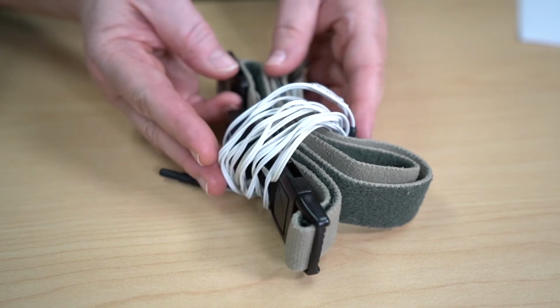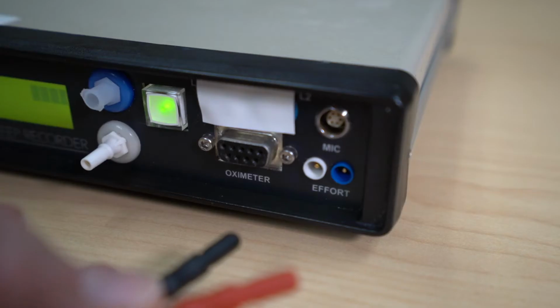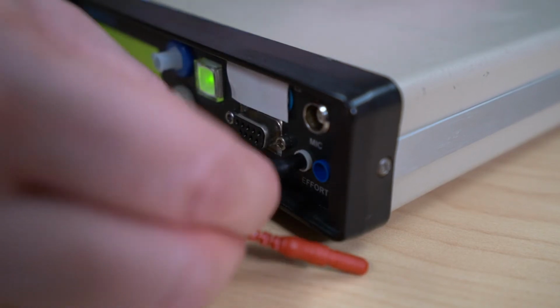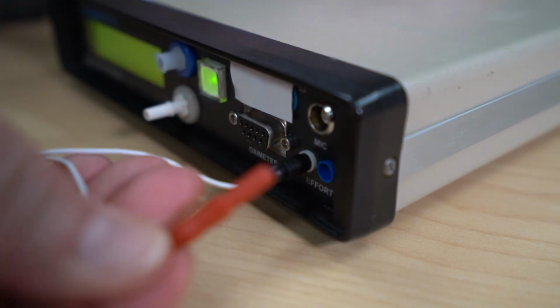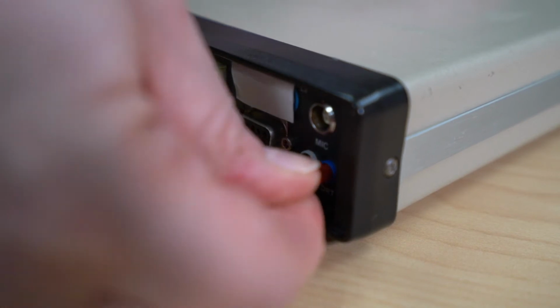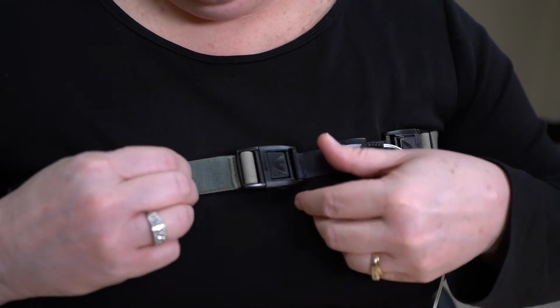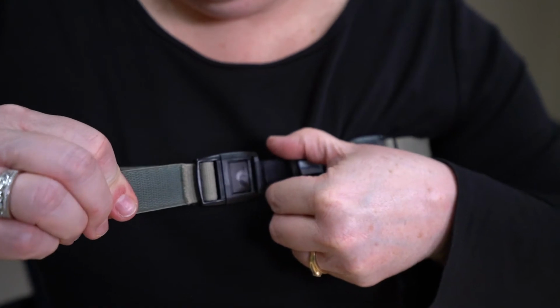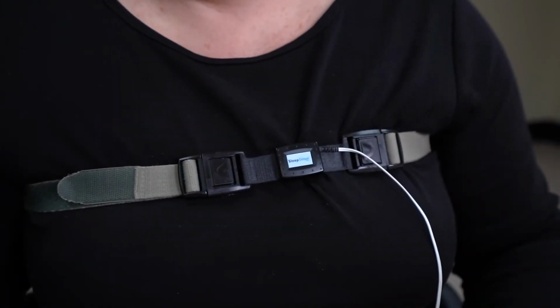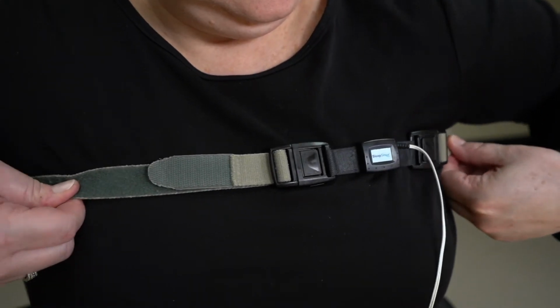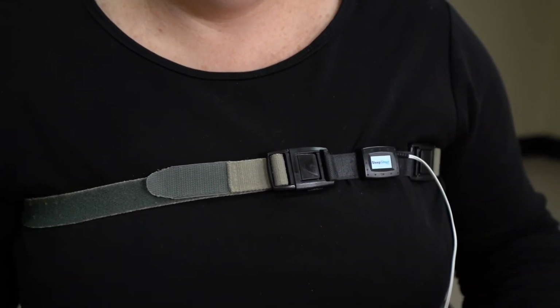Next is the effort belt. Locate the effort port on the recorder. You will firmly insert the black wire into the white receptacle and the red wire into the blue receptacle. To apply the effort belt, wrap the belt snugly but comfortably around the top half of your chest at the height of your shoulder blades above the nipple line. Position the belt with the emblem and white wire offset to the left or right side of your chest.